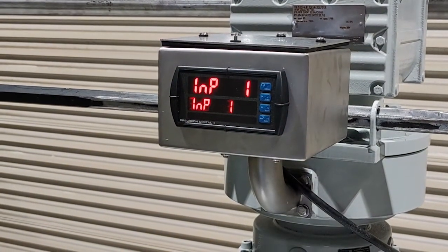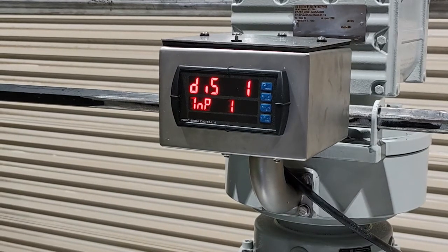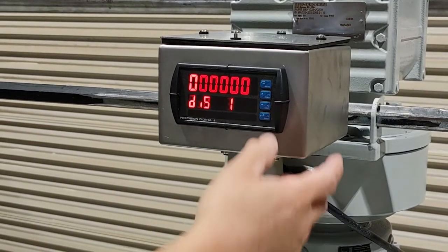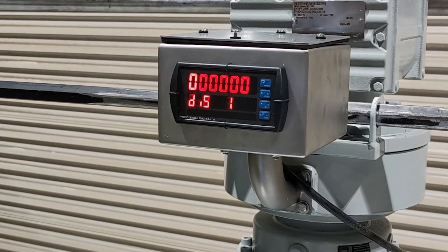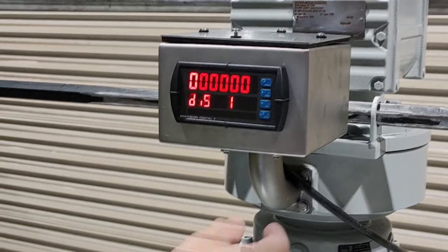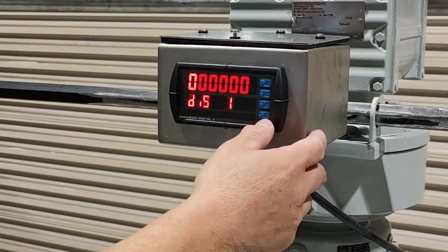The screen will blink 3 times to show that the signal is being collected, and it will display DIS1 when the signal is stored. Press the Enter button to confirm the value you want the screen to display when the load cell reads the stored signal. For the rest state set point, the display should read all zeros. Press the Enter button to confirm the setting.